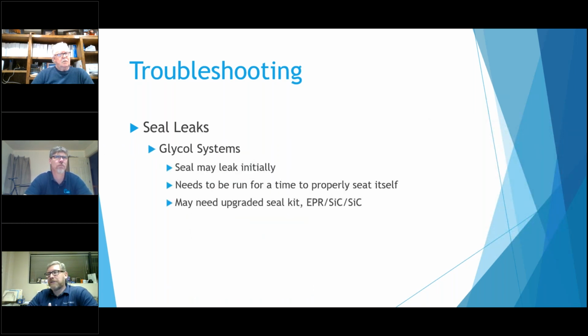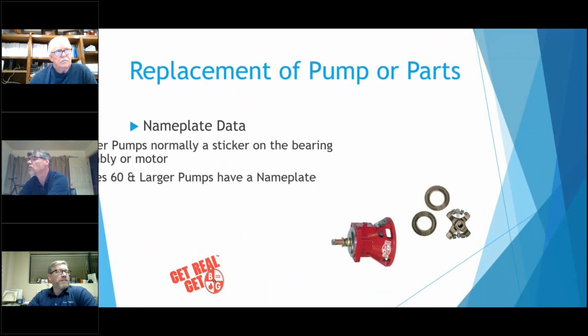Glycol seals, we see them leak initially sometimes, but there is an upgraded seal. If there's too much glycol, usually above 35%, I start to think about putting them in if you're having a lot of leaky issues. It used to be they leaked initially, but now everyone pretty much uses the premixed stuff, so you don't have those kinds of issues. Replace the pumps.